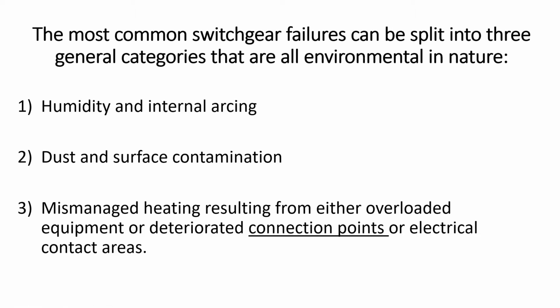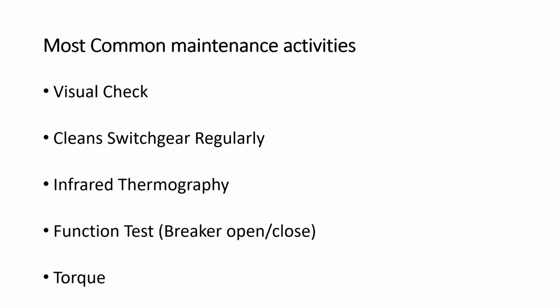Mismanaged heating results from either overloaded equipment or deteriorated connection points—and again, it's the terminations. Where the wires terminate, that's your biggest point of failure. Okay, most common maintenance activity: visual. So which visual?